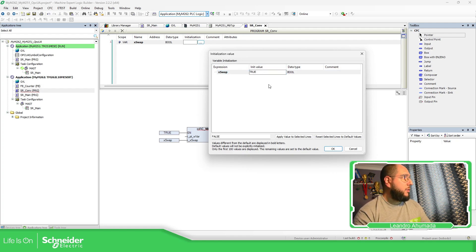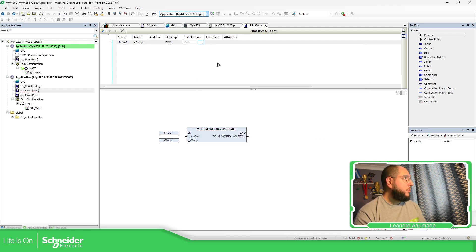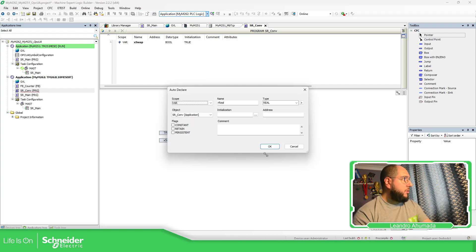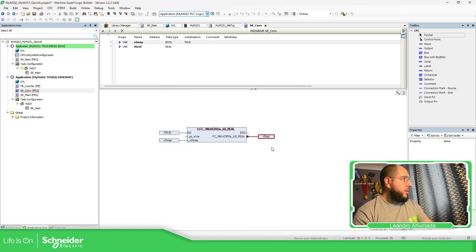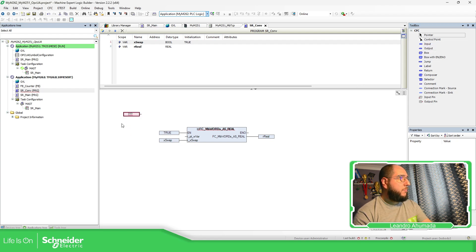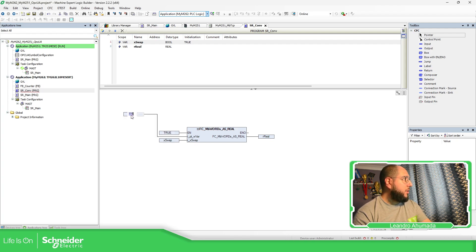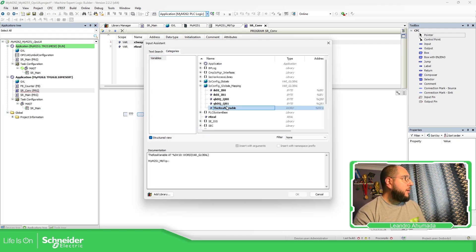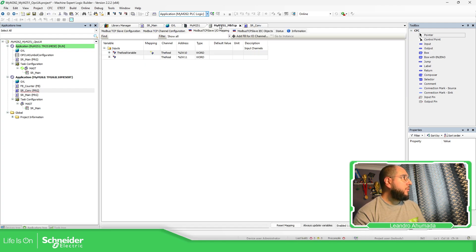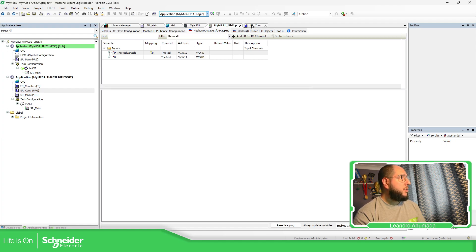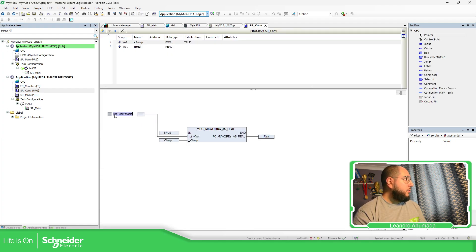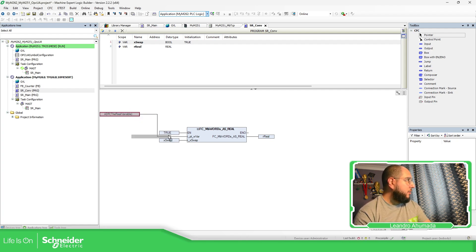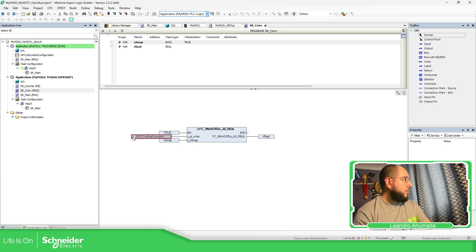Here we just need to add the variable that I'm going to use, so it's going to be real, real variable. And here we just need to add the ADR, so I'm going to add this input here and select the variable that I need. IOConfigGlobal, the real variable, the one that I have added. This came from here or we can use the %IW10. To this variable what we need to add is the pointer ADR, the address pointing to that. And then we need to call this into the master.